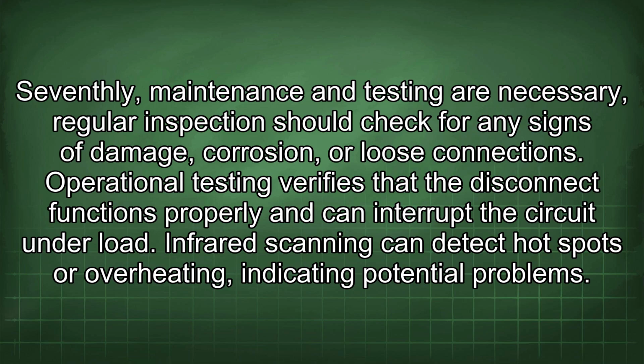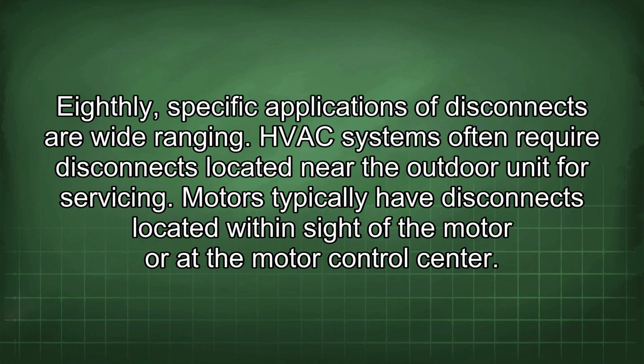Operational testing verifies that the disconnect functions properly and can interrupt the circuit under load. Infrared scanning can detect hotspots or overheating, indicating potential problems. Eighthly, specific applications of disconnects are wide-ranging. HVAC systems often require disconnects located near the outdoor unit for servicing.